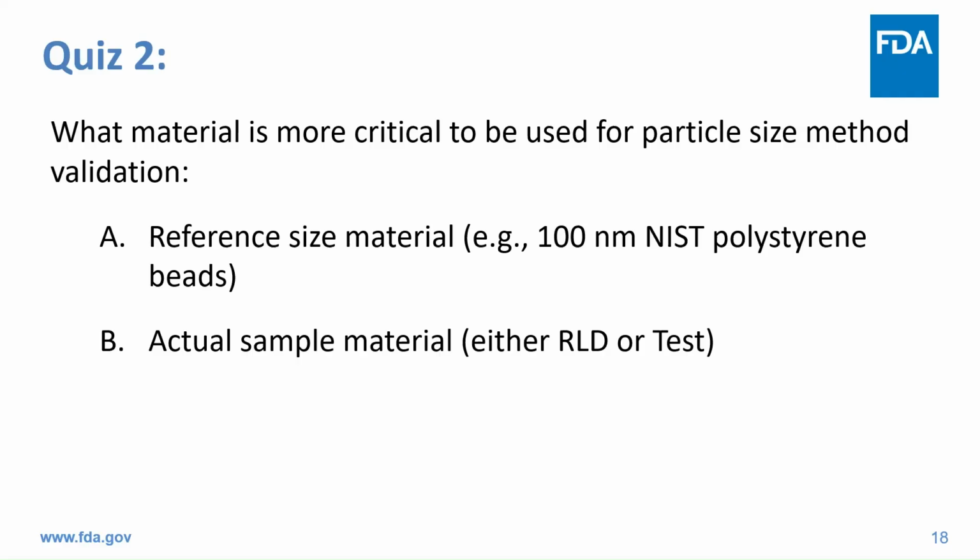I think I just gave you the answer a minute ago. Yes, it's the actual sample. It's much more valuable than using a reference size material. It's not that the reference standard is not useful. It is useful for qualification, but it can only give you that much confidence about the instrument. Is it working? That's it.